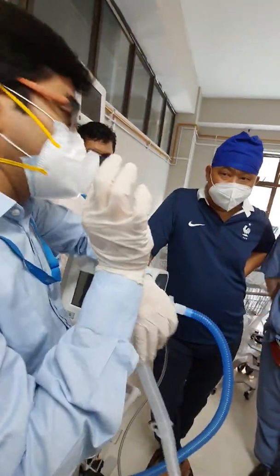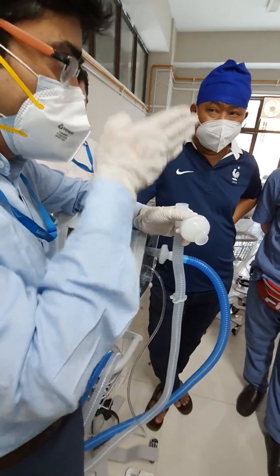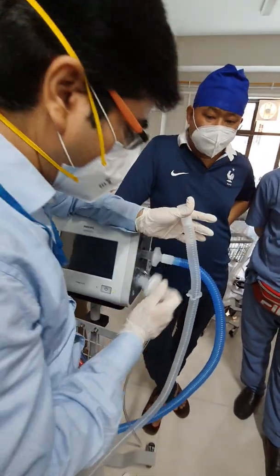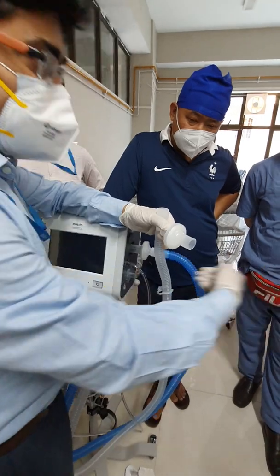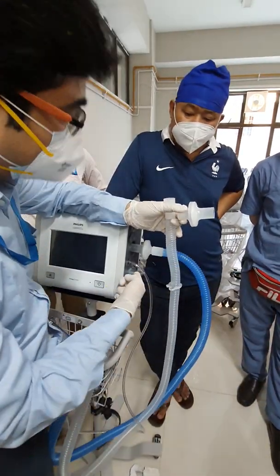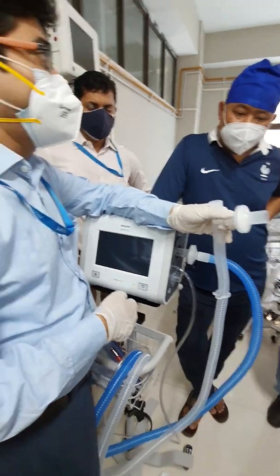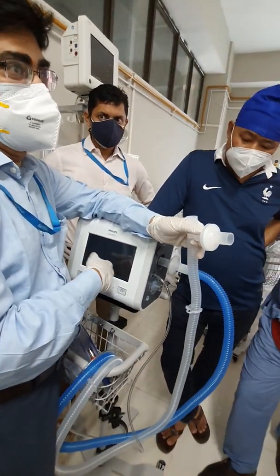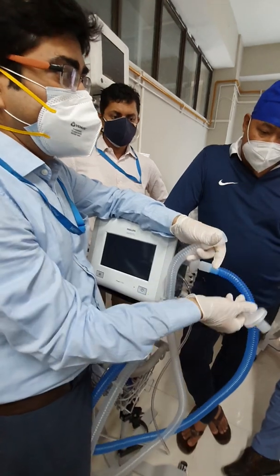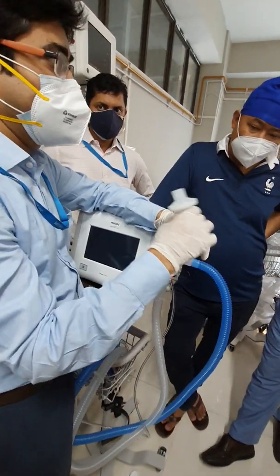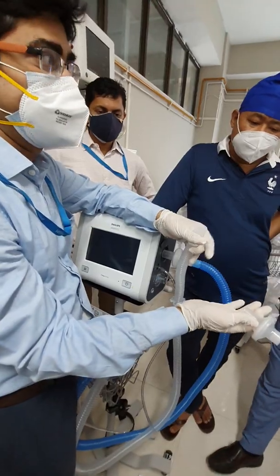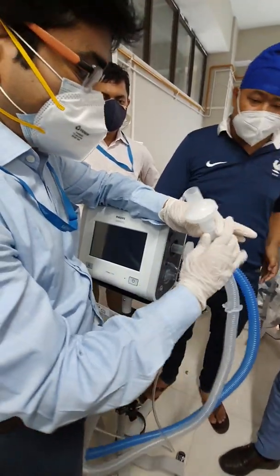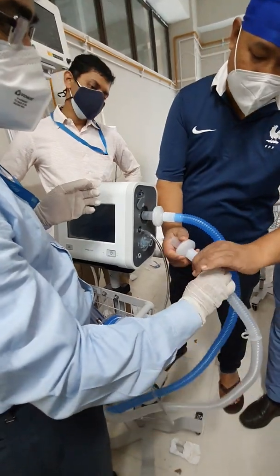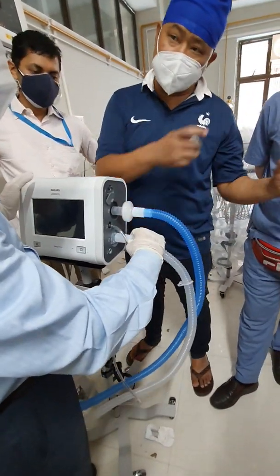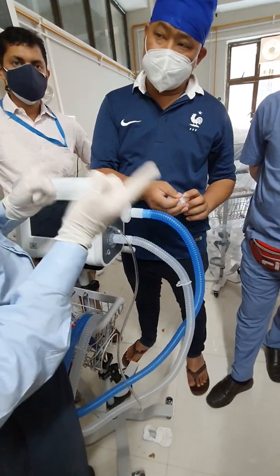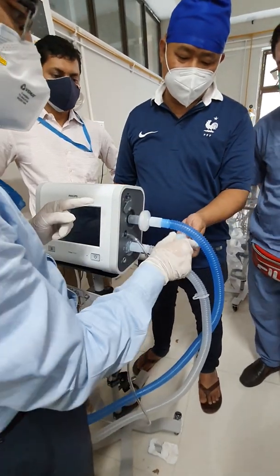HME is heat moisture exchange. If I put an HME here, the exhalation flow will carry moisture into the machine, and it will definitely break down the circuitry inside. So the HME should be towards the patient end, so that you can avoid dry air or dry oxygen. Instead of this one, we can connect directly like this and put the HME at the patient end. HME will not protect against virus and bacteria.